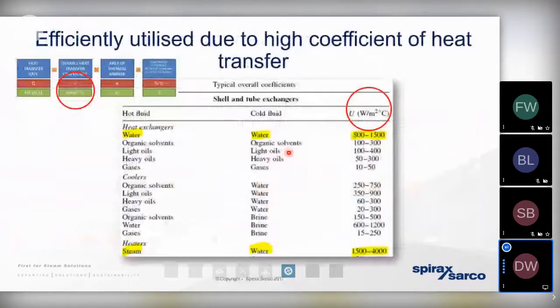So as far as steam to water heat exchangers are concerned, especially plate heat exchangers, it's that U value, that heat transfer coefficient, that is perhaps the most interesting, as this refers to the speed of heat transfer as it moves across that thermal barrier. And you can see from the chart above that the heat transfer coefficient of steam is about 3 times greater than that of water. So that means we've got a greater U value, and therefore we only need a smaller heat transfer surface area. We need a smaller A value.